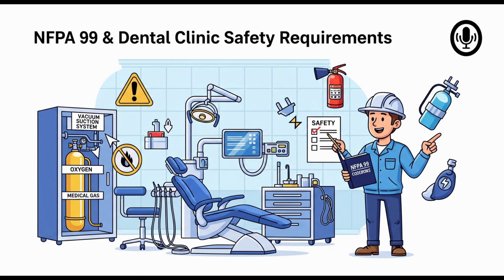Ah, interesting point. Section 5.3.3.7 handles Category 3 vacuum. It mostly refers back to the general requirements in 5.1.3.7, which apply to Categories 1 through 3, but it does allow for some Category 3 specific exceptions. Now, that general section, 5.1.3.7, does typically require multiple vacuum pumps. Enough capacity so the system works even if the largest single pump is out of service. It also requires things like automatic backflow prevention, isolation valves, and a receiver tank. So vacuum might still need redundancy, even in Category 3.